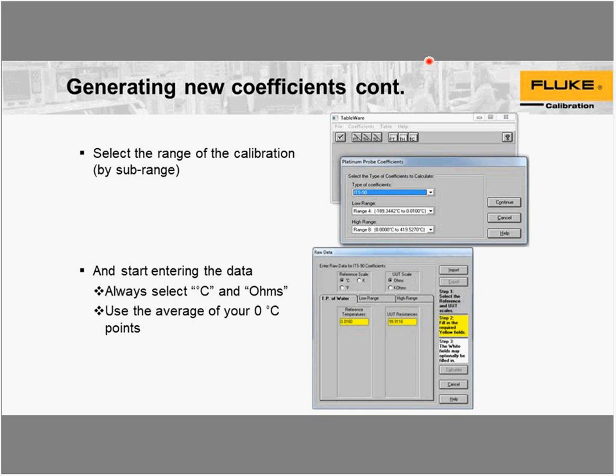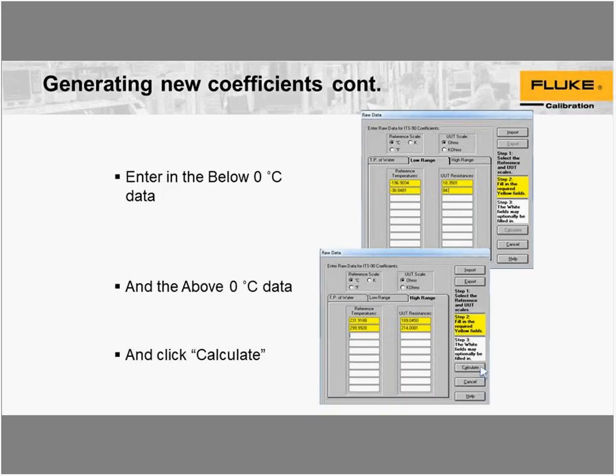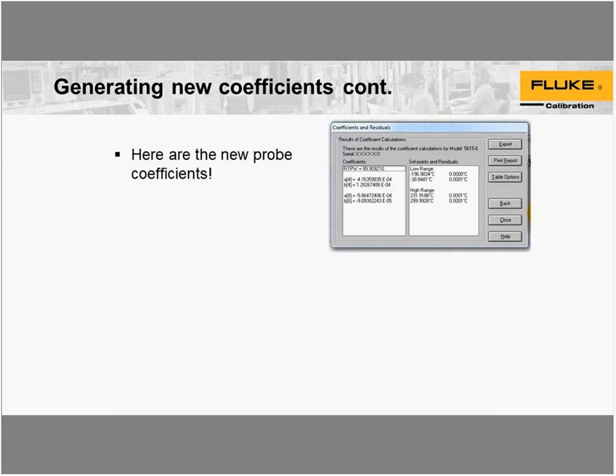I've already put in the 0 value, the reference thermometer 0 value, and the resistance from the probe system combination. Next, we go to the low range. So put in the liquid nitrogen numbers at -196 and the resistance of the DUT or UUT at 18.3501 ohms. Move to the -38 point. We put that data in there. Then the last thing we do is click over onto the high range tab, and we add the data for the high range. And then we hit calculate. Okay. All right. It's easy as that.